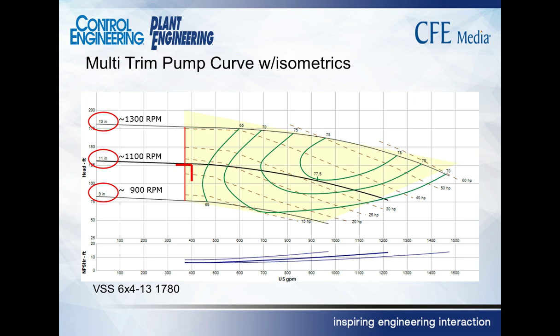6-inch suction line, 4-inch discharge, 13-inch impeller. It's a 4-pole motor running 1780. Here's a different pump that does. This pump is provided with a 13-inch impeller, and it's been trimmed down to a little over 11 inches, right at 11 inches, to meet this particular operating point.